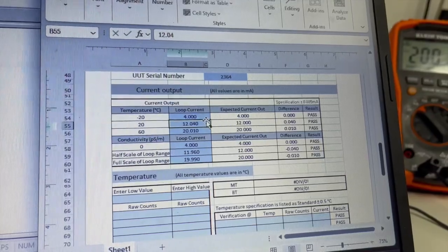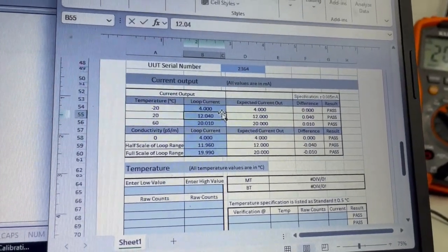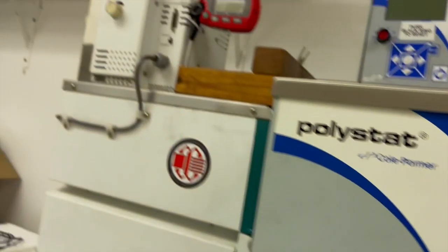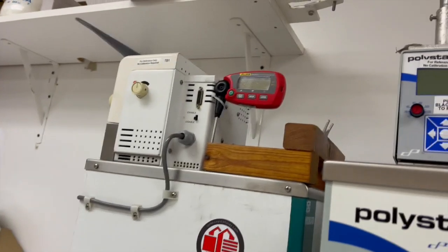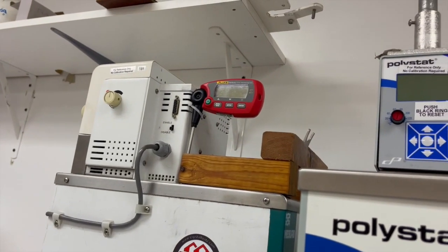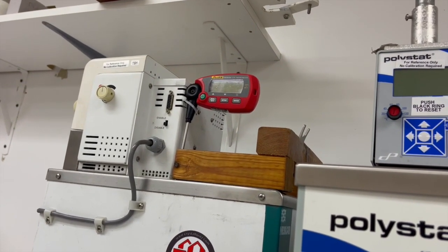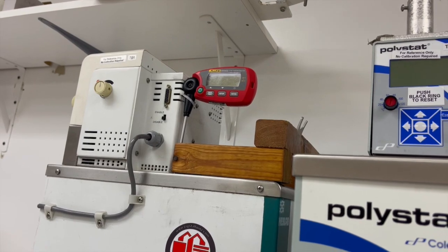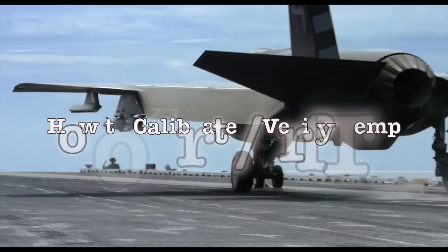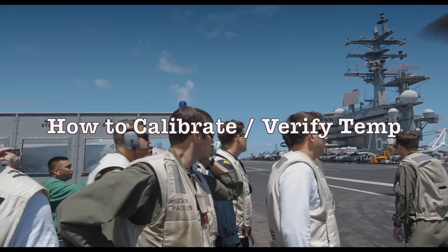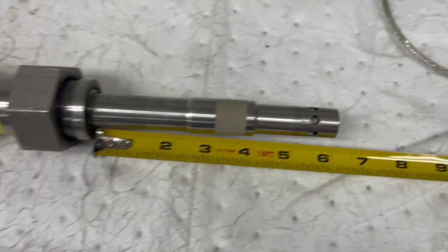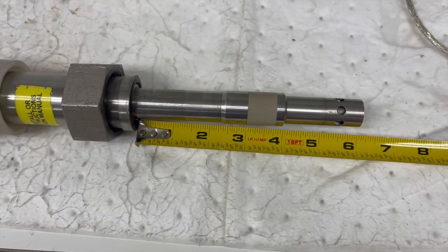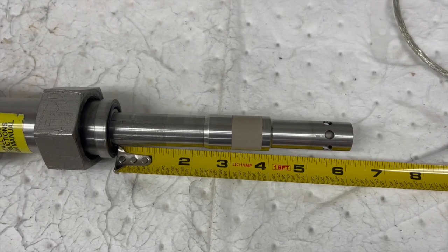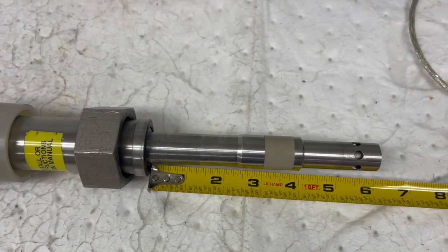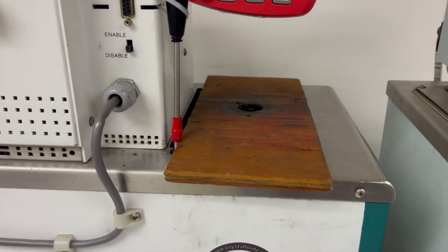So for that, what we always do first is the temperature first. For that, you need the temperature bath and the temperature probe that we're going to sell you as part of the kit and all of this other equipment. Now we're going to calibrate and verify temperature. One of the things that we do is we measure out a 6-inch insertion depth for the JF-1A into the temperature bath.